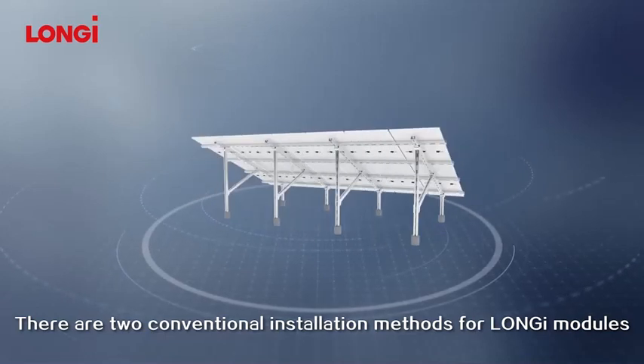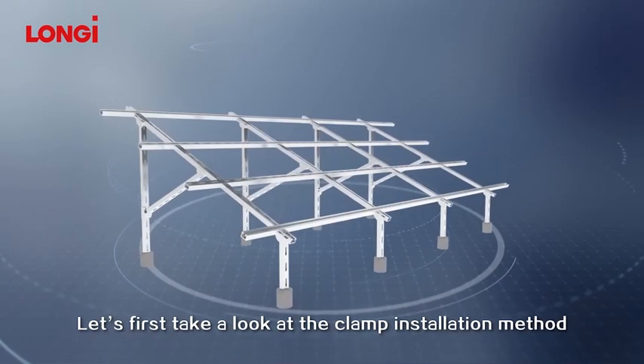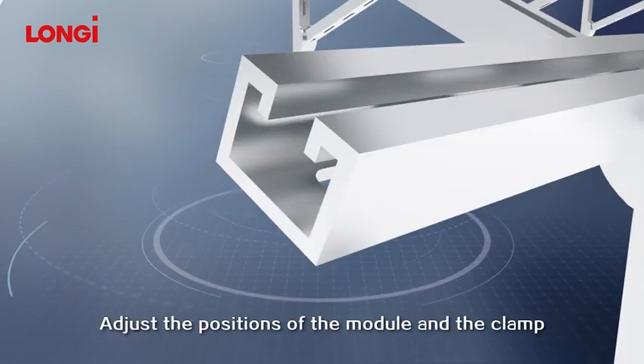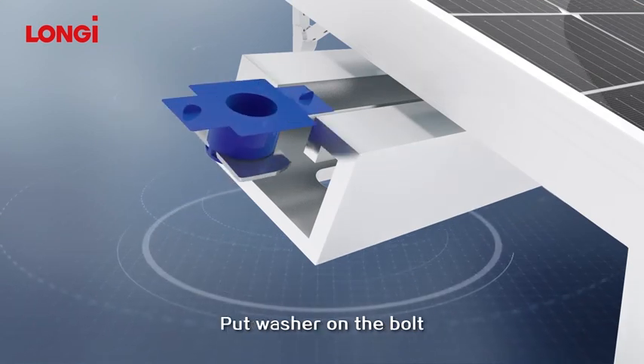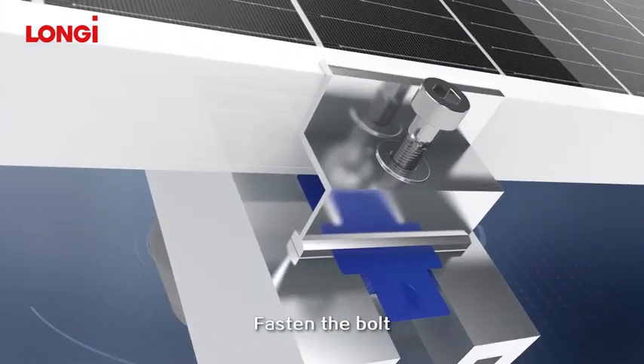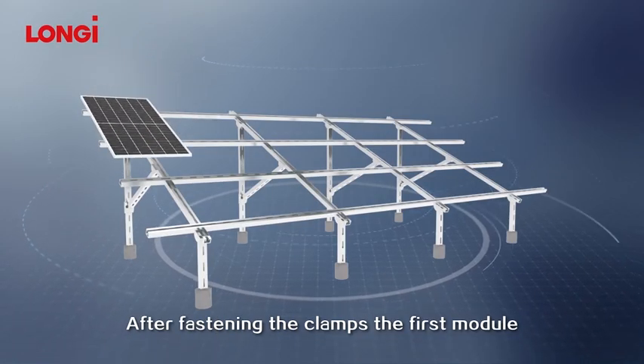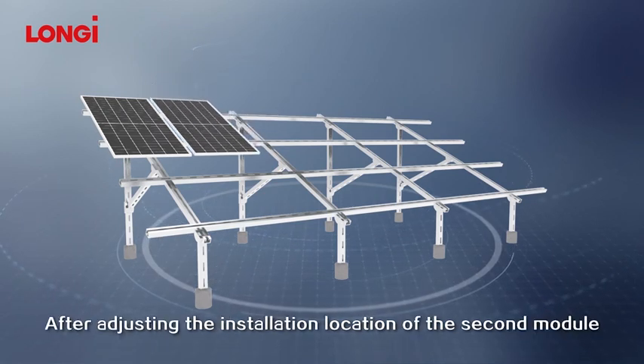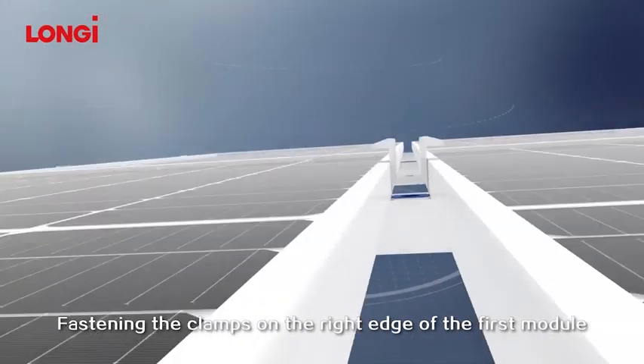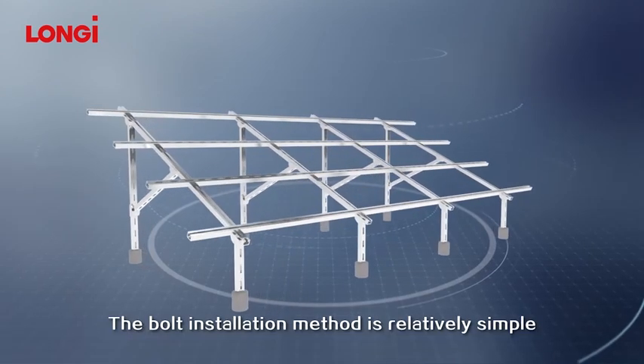There are two conventional installation methods for LONGi modules: using bolts and using clamps. For the clamp installation method, first place the outer module. Adjust the positions of the module and the clamp according to design requirements. Put a washer on the bolt, pass through the clamp and the supporting system, then put on washer, spring washer, and nut. Fasten the bolt — the torque should be 14 to 20 newton-meters. After fastening the clamps on the first module, place the second module, adjust its installation location, then place the clamps between the two modules.